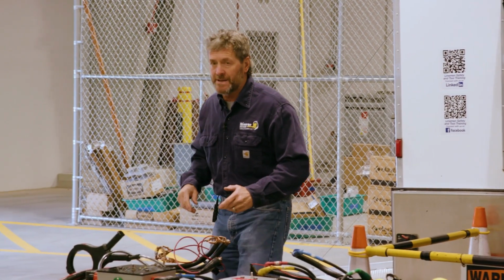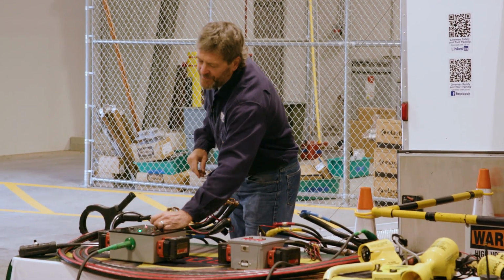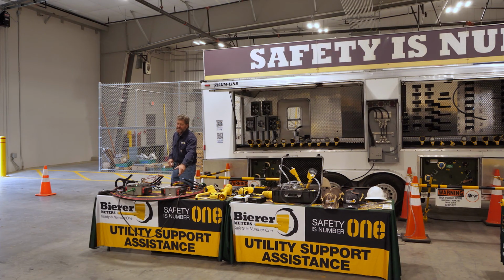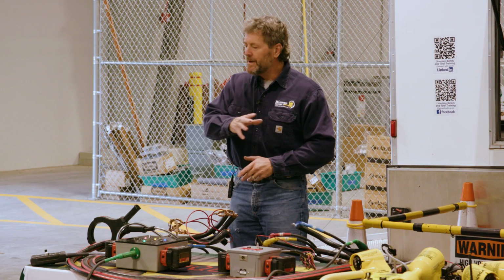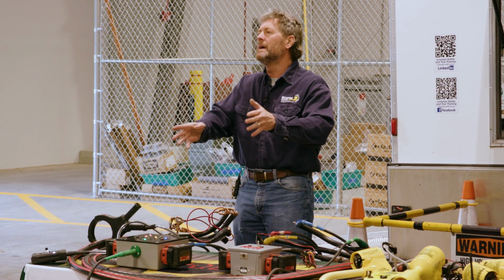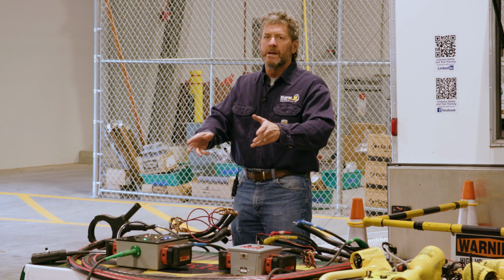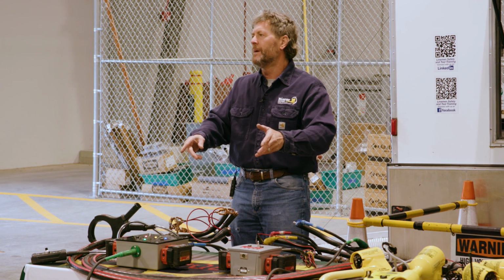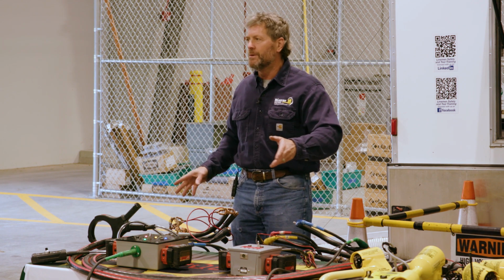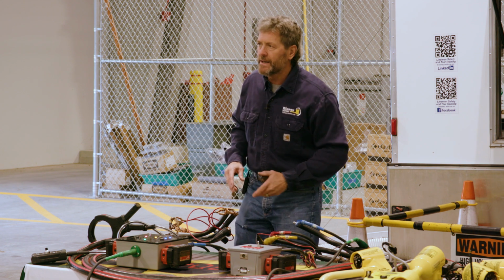I'm going to talk some psychological safety in a moment, but first — we've got a 3-phase ID and a single phase ID. I'm going to skip the single and go straight to the 3, because it does what the single does, times 3. It gives you A, B, or C on a de-energized primary cable, and it goes through about 2 to 3 splices. After 3, it loses too much of the load, the pulse, and you can't read it anymore. But up to 3, it does good.